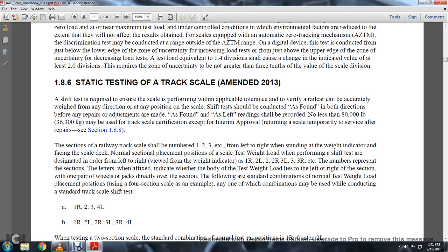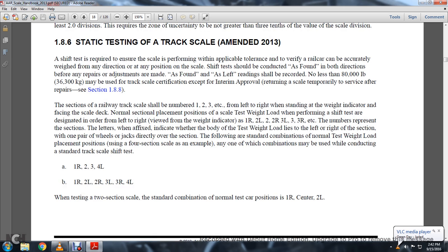1-8-6: Static Testing of the Track Scale, Amended 2013. A shift test is required to ensure the scale performs within applicable tolerance to verify that a railway car can be accurately weighed from any direction and in any position on the scale. The shift test should be conducted as found in both directions before any repairs or adjustments are made; as-found readings shall be required. Not less than 80,000 pounds may be used for track certification except for Interim Approval for returning the scale temporarily to service after repairs. The sections of the railway track scale shall be numbered 1, 2, 3, 4, etc.